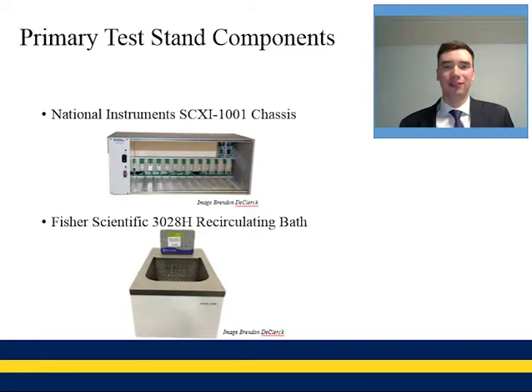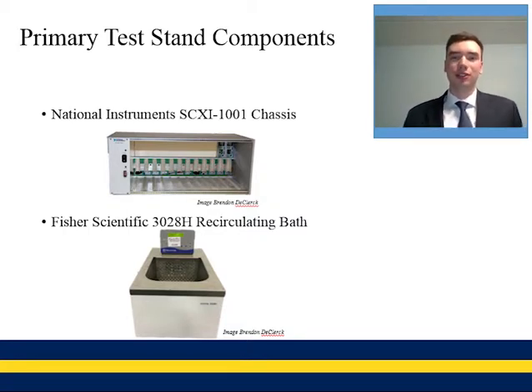We also have the test stand design that we've been doing in this project. Some major components of this test stand are the National Instruments SCXI 1001 chassis. This is the main brain of our system. It's a data acquisition system that can hold up to 12 modules. We're using 5 modules in it, so we're able to read thermocouples and analog inputs. We're able to output analog signals, and we're also able to output digital signals, and there's also a high voltage relay switching board.